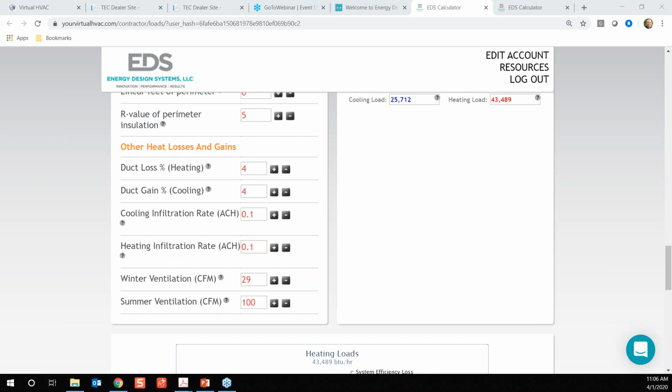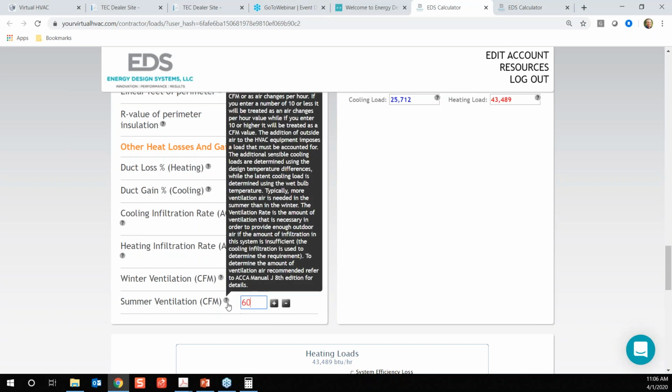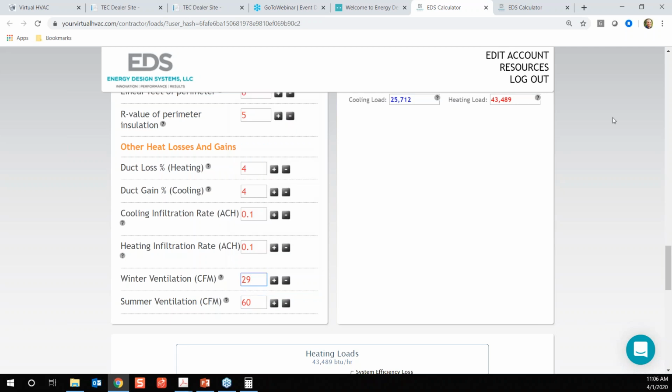So it's complicated to do it this way, but let's say my ERV is dropping my 90-degree outside air down to 84 degrees. So 6 of my 15 degrees. So 6 divided by 15, that's a 0.4 improvement. That means it's 0.6 not improved, for 0.6 times my 100. So I'd still have to deal with 60. So you might do something crude like that.